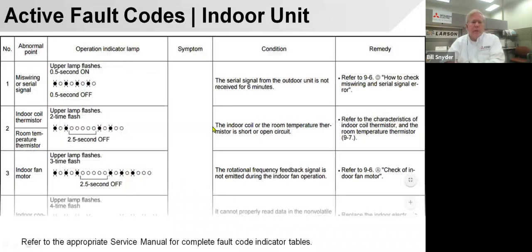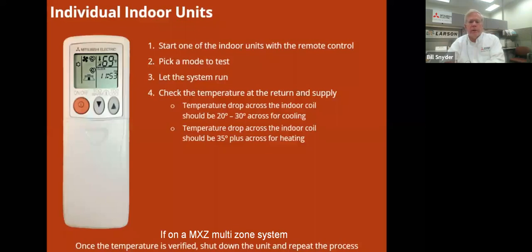And this is still on the indoor unit. This is the type of fault codes you would see: miswiring. If it was just blinking on, off, on, off, on, off, it would be a miswiring signal. This would be a 2 flash, would flash twice, and then there'd be a 2.5 second pause and flash twice. And this is telling you it's a room temperature thermistor. You have to make sure you grab the codes for the correct piece of equipment. They could be different. Some of them are exactly the same, but make sure you're on the right model number when you're checking these things out.